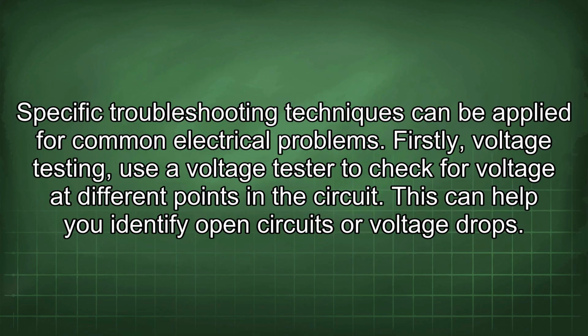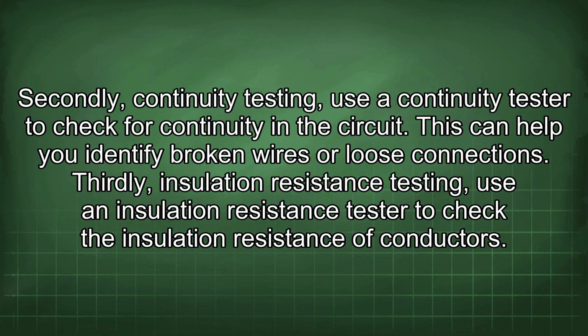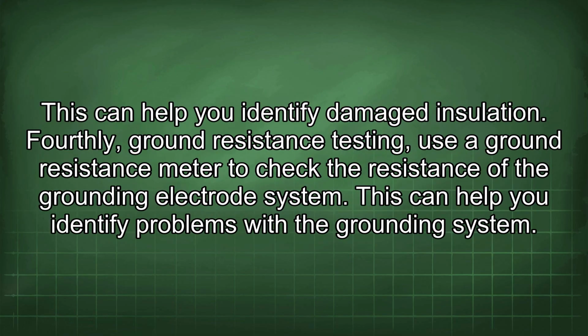Specific troubleshooting techniques can be applied for common electrical problems. Firstly, voltage testing. Use a voltage tester to check for voltage at different points in the circuit. This can help you identify open circuits or voltage drops. Secondly, continuity testing. Use a continuity tester to check for continuity in the circuit. This can help you identify broken wires or loose connections. Thirdly, insulation resistance testing. Use an insulation resistance tester to check the insulation resistance of conductors. This can help you identify damaged insulation. Fourthly, ground resistance testing. Use a ground resistance meter to check the resistance of the grounding electrode system. This can help you identify problems with the grounding system.